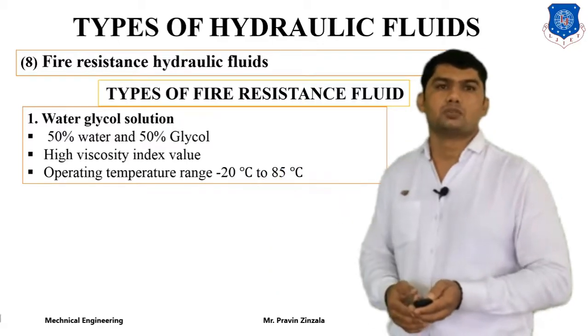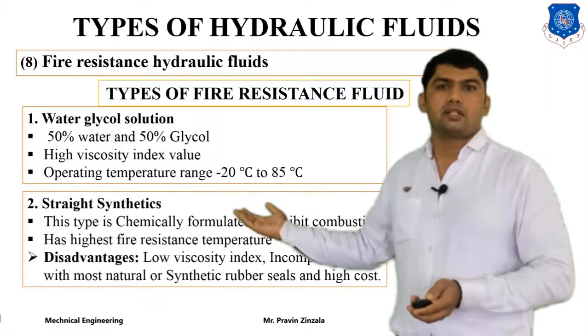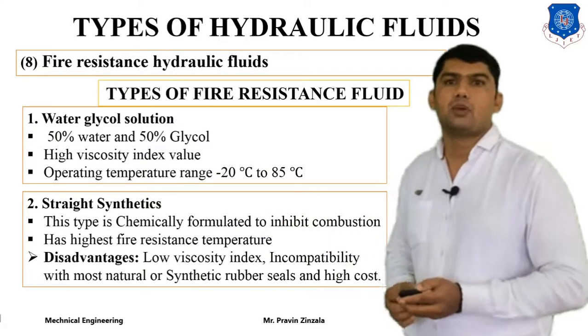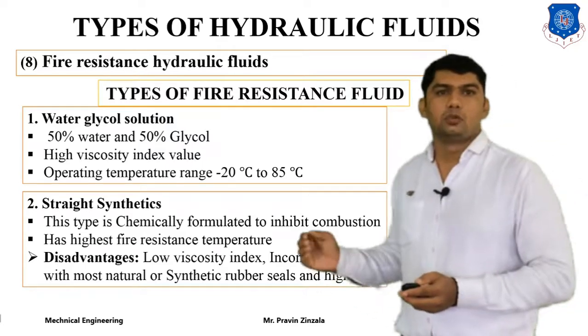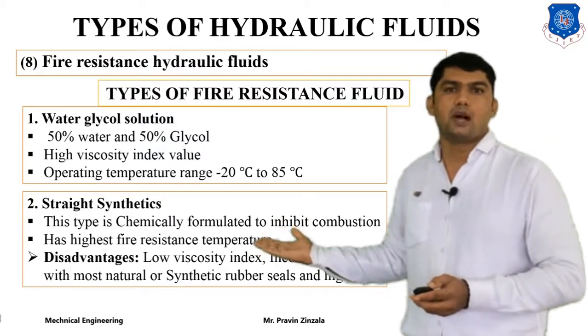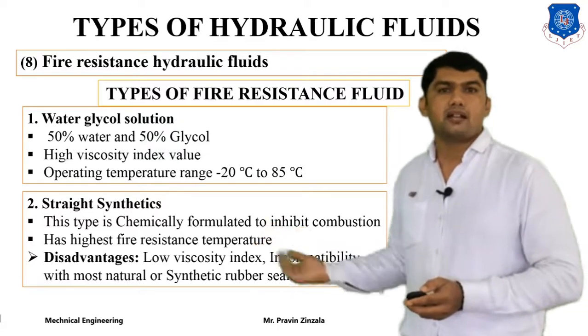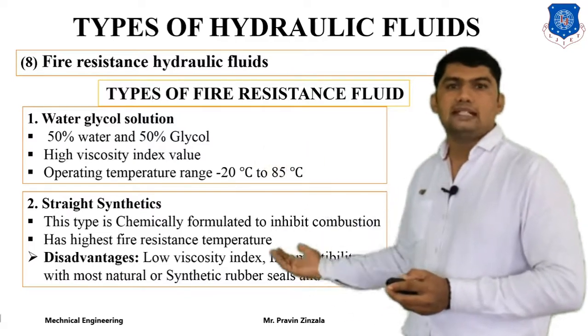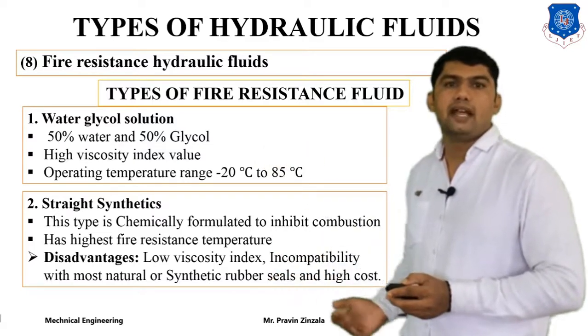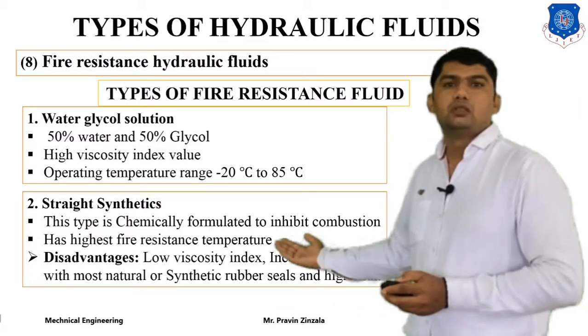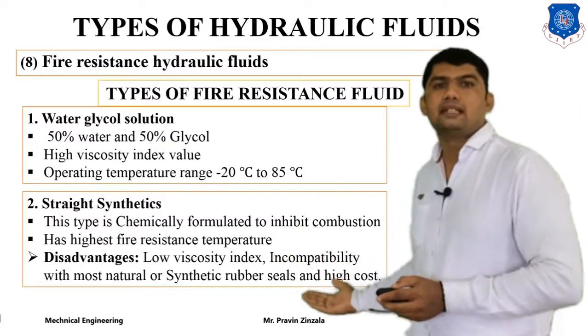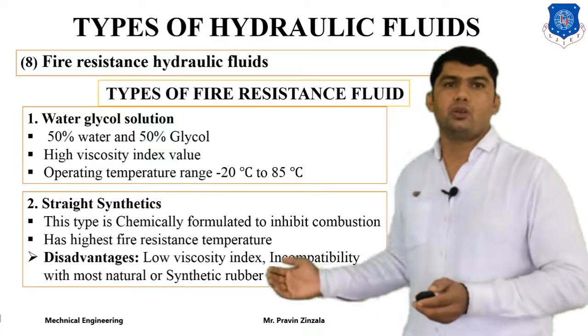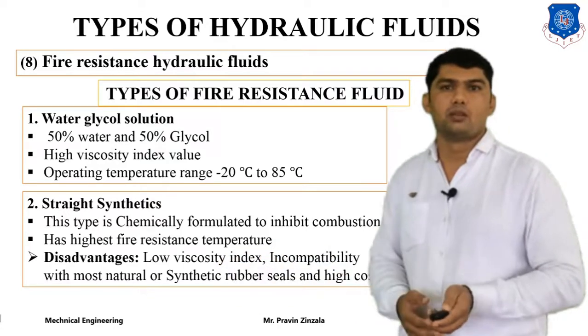The second type is straight synthetics, which is a chemically formulated inhibitor against combustion, also used for higher temperature operations of hydraulic systems. It has higher fire resistance temperature compared to water glycol solution. The disadvantages are low viscosity index, incompatibility with most natural or synthetic rubber seals, and high cost — so you cannot use rubber seals with this type of hydraulic fluid.